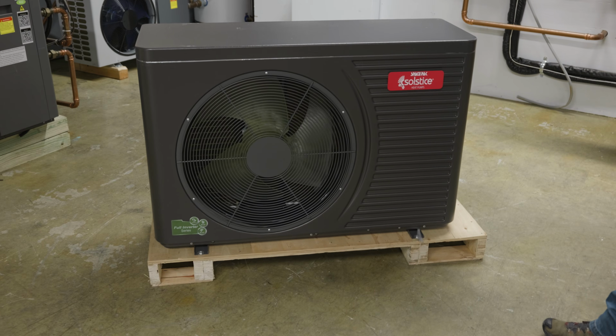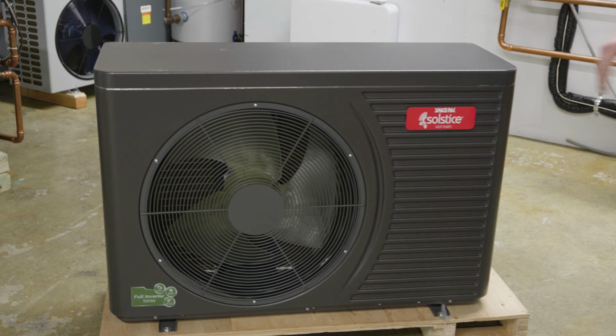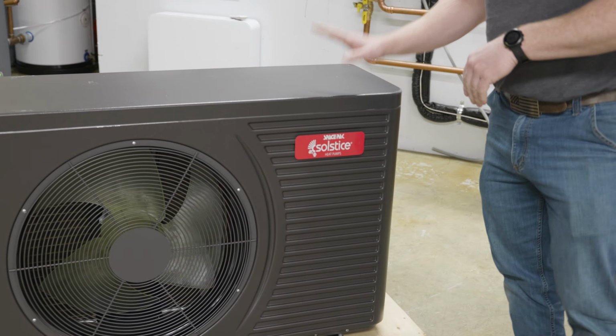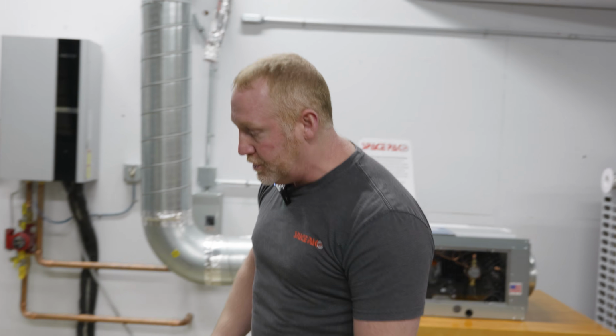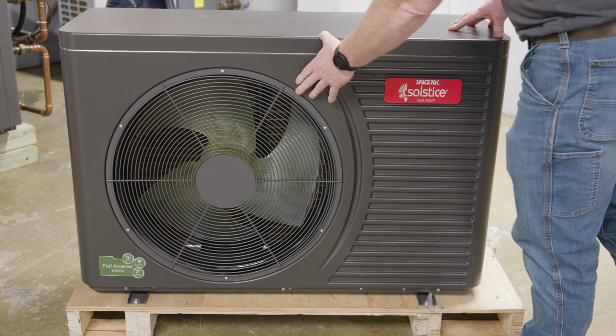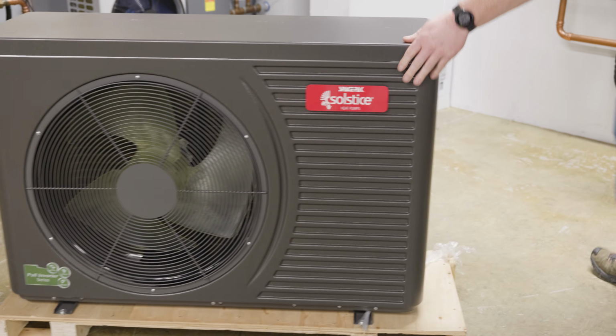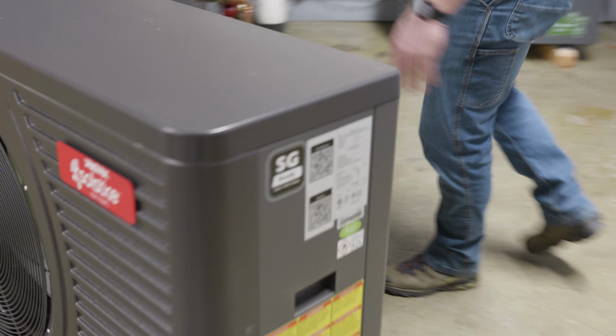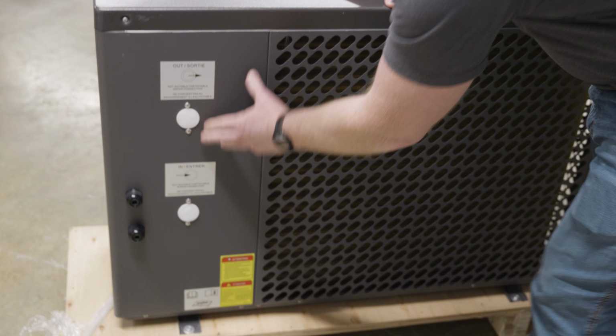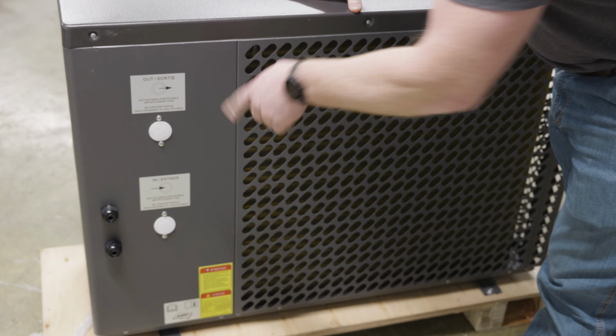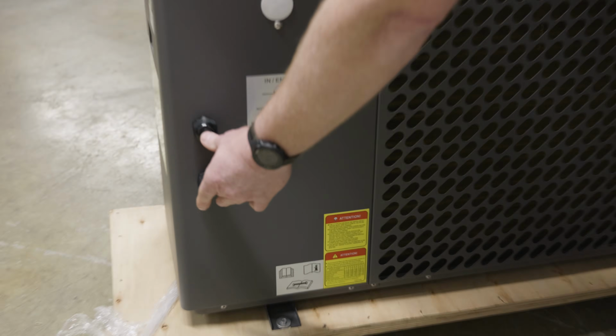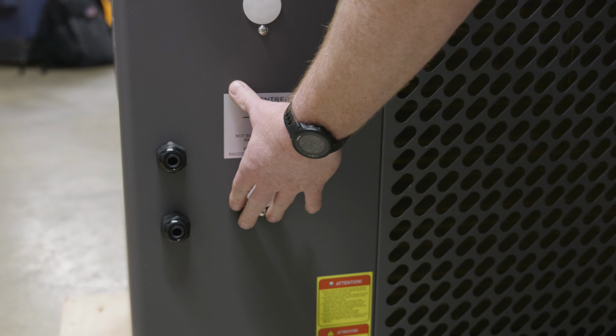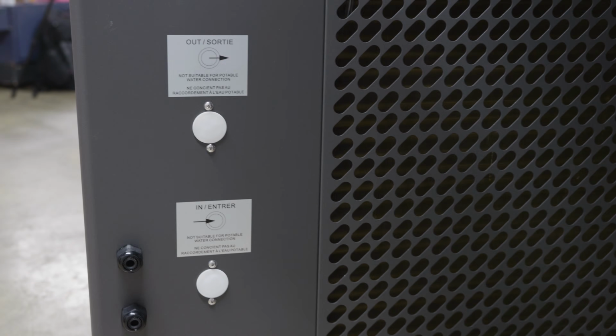This particular unit is a CC32-18, the smallest of our series of 3 air-to-water heat pumps in R32 refrigerant. Discharge air comes out the front, SpacePak logo. We walk around the back. This is where the magic starts to happen. Our inlet and outlet water temperature connections, 1-inch tappings. Our high and low voltage control wiring as well comes in the back right-hand side of the unit.